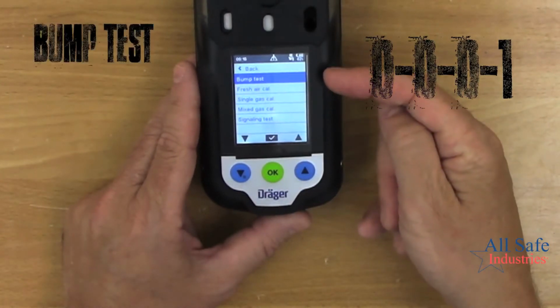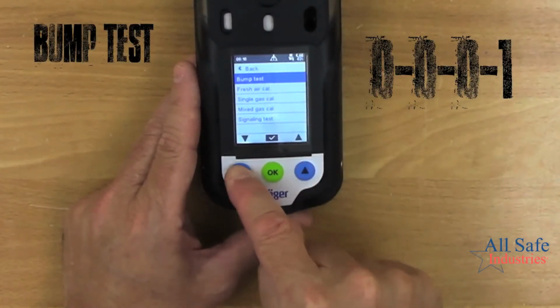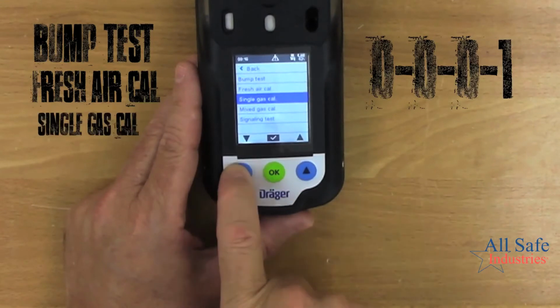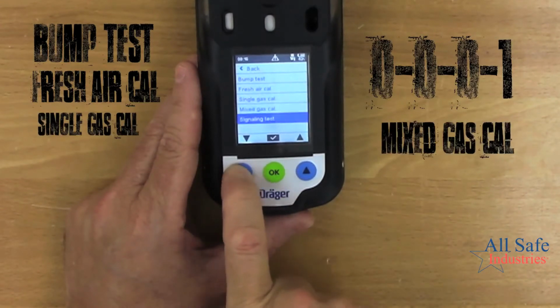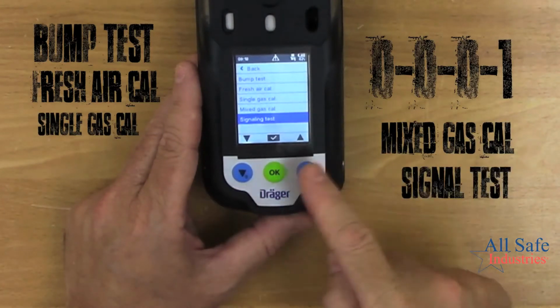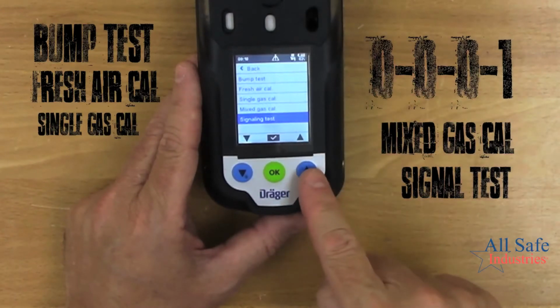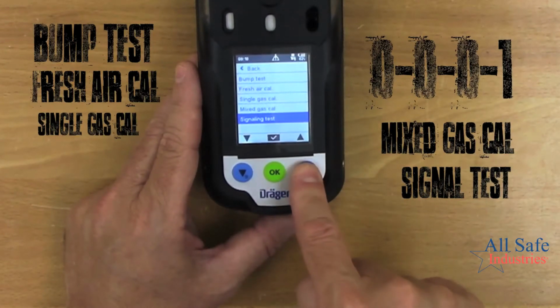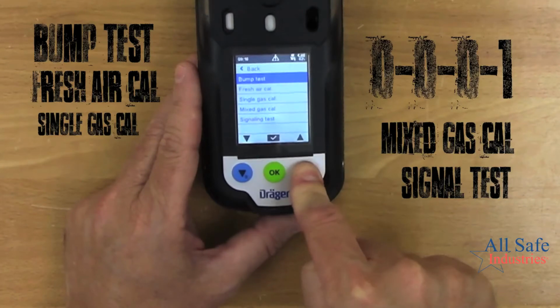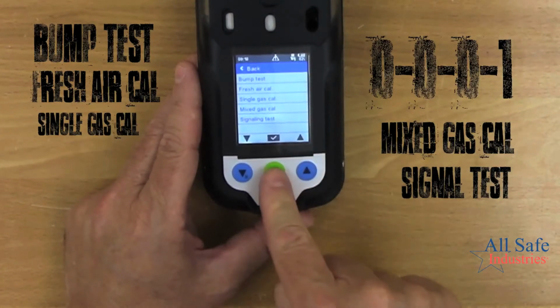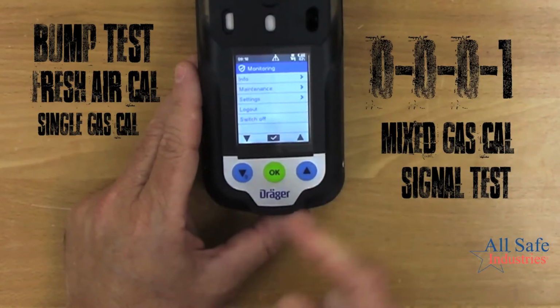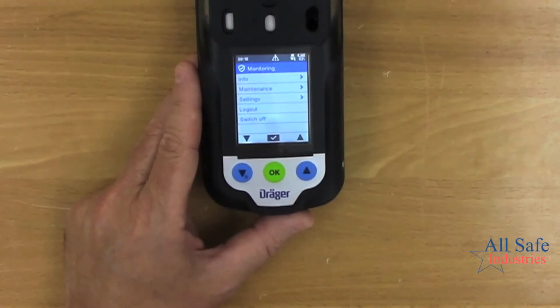Now I can run a bump test, a fresh air cal, a single gas cal, a mixed gas cal, and I can still do a signal test. So you get more features once you're logged into the menus, and that's a way to keep people who haven't read the manual yet from getting in and changing settings on your instrument.